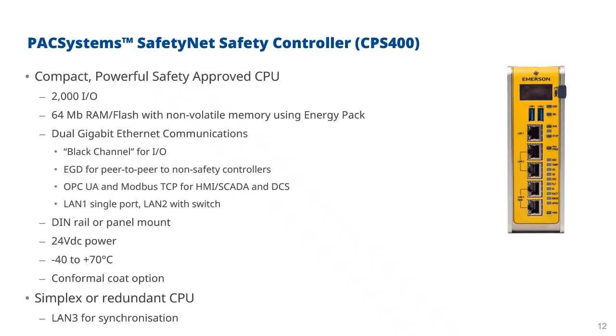And it's up to the user what they want, but effectively, it's just one extra cost inside the system to be able to get that higher level of availability. So I would expect most people will go for a redundant CPU just to get that higher level of availability. Otherwise, your plant is stopping when there's a failure, and that can be extremely expensive.